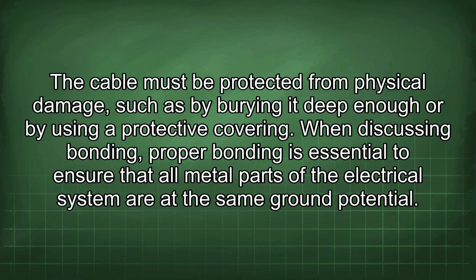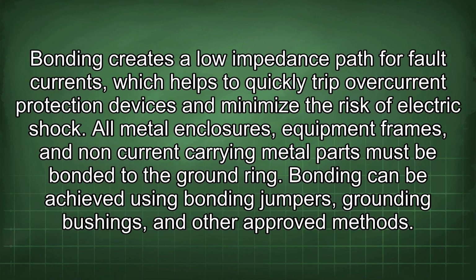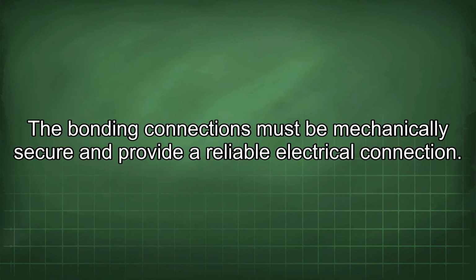When discussing bonding, proper bonding is essential to ensure that all metal parts of the electrical system are at the same ground potential. Bonding creates a low impedance path for fault currents, which helps to quickly trip overcurrent protection devices and minimize the risk of electric shock. All metal enclosures, equipment frames, and non-current carrying metal parts must be bonded to the ground ring. Bonding can be achieved using bonding jumpers, grounding bushings, and other approved methods. The bonding connections must be mechanically secure and provide a reliable electrical connection.